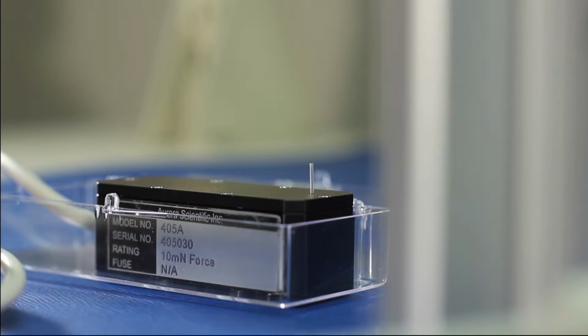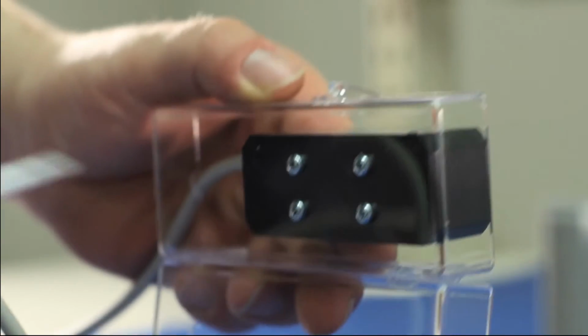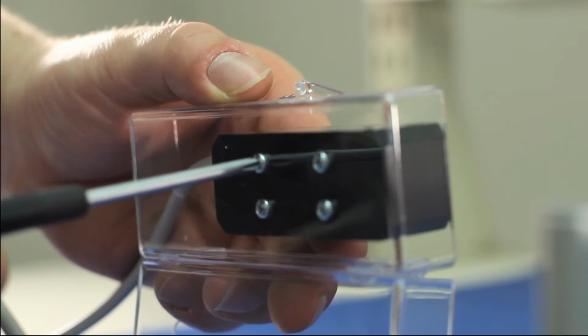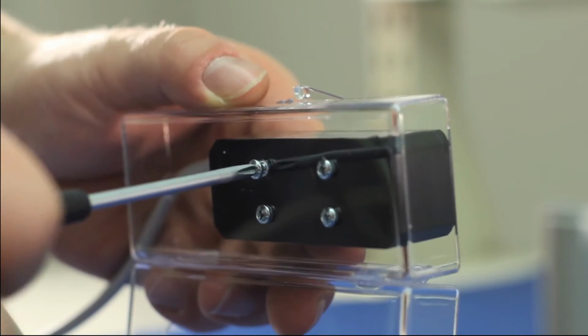If at any point you hear the transducer beeping continuously, stop touching the glass output tube and proceed more gently. The beeping is the overload warning for the unit. Using a Phillips head screwdriver, carefully remove the 4 screws holding the transducer in its plastic case.